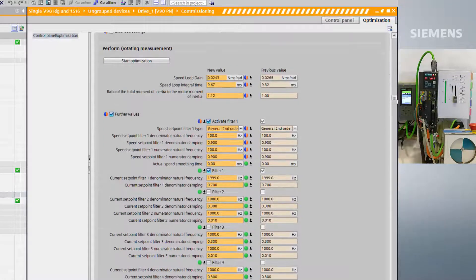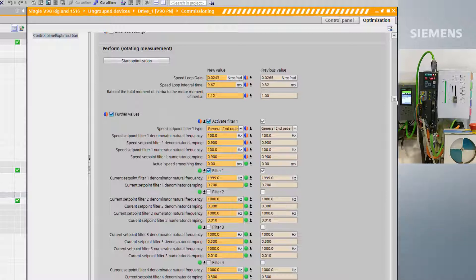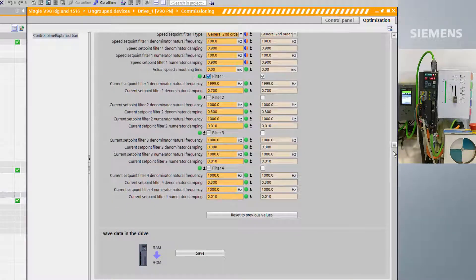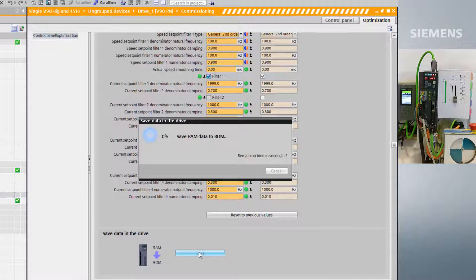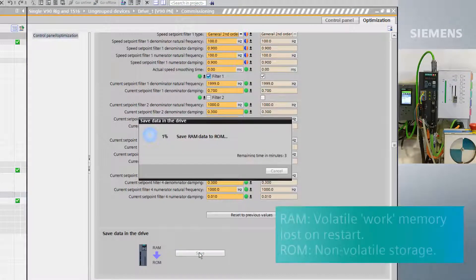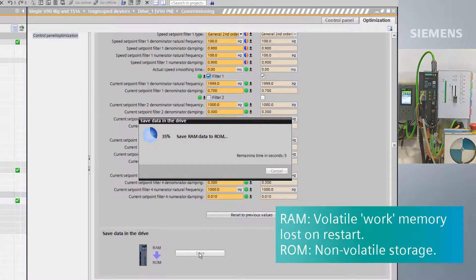At present, the values are only held in the online RAM memory of the drive, so we must perform a RAM to ROM in order to retain the values after a power cycle.